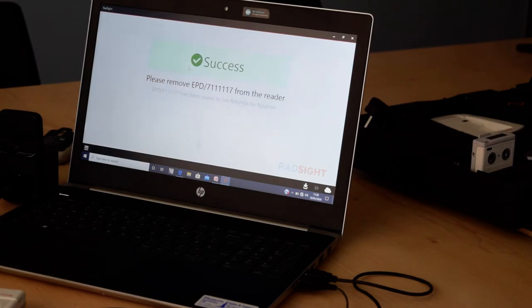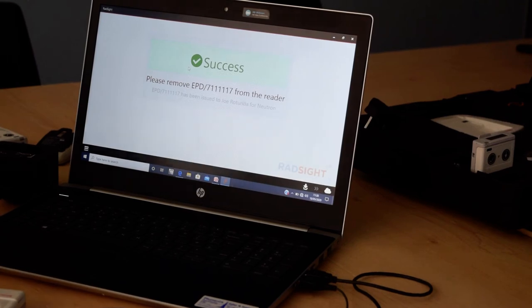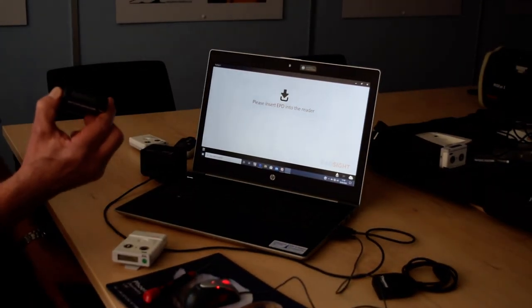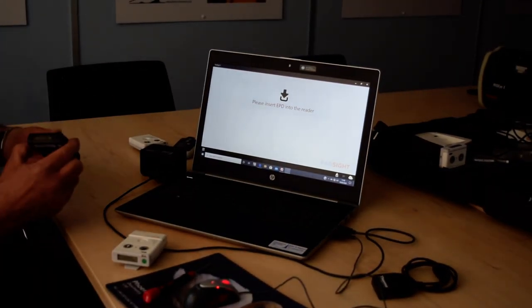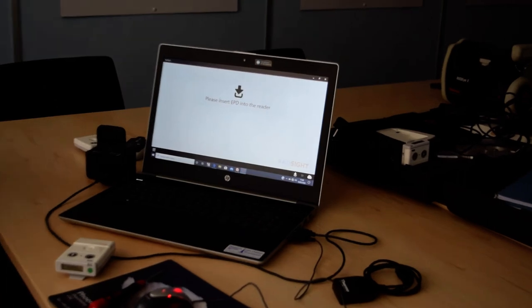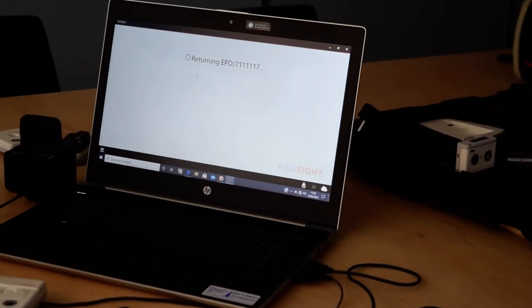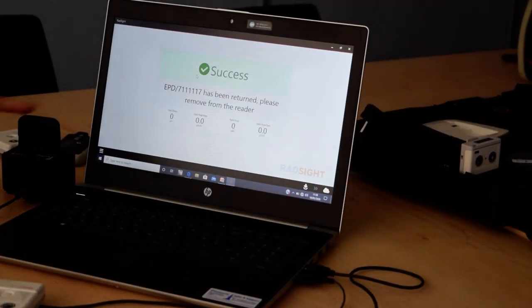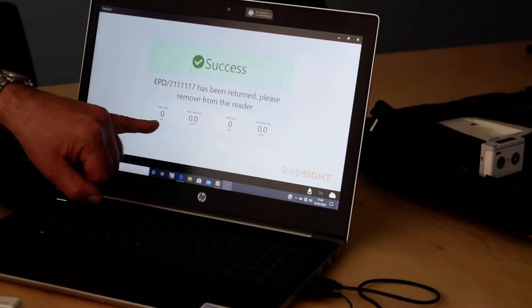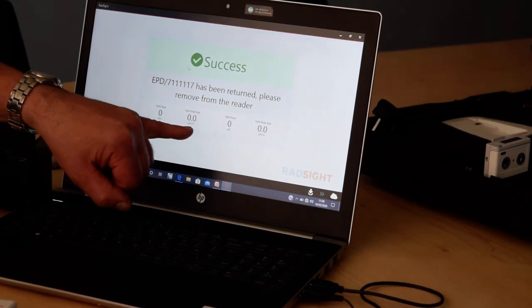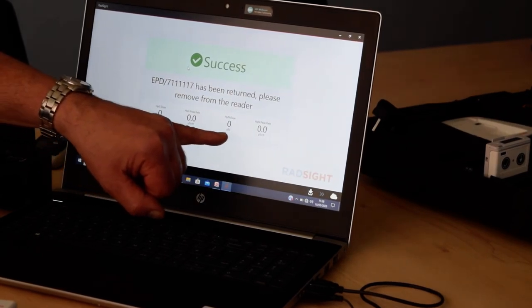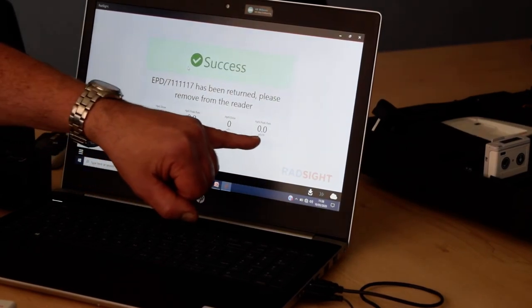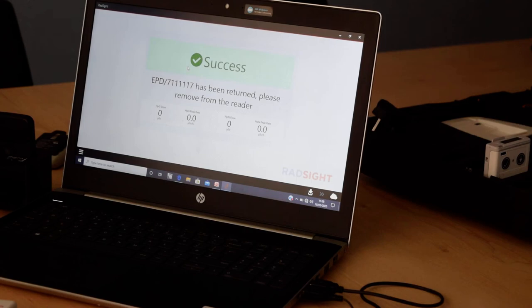It's issued the dosimeter, it's switched it on, that's now recording both the gamma dose and the neutron dose, and when it's returned back into the docking station, it then gives you the actual H star 10 cumulative dose, dose rate, and also the neutron cumulative dose and neutron dose rate.